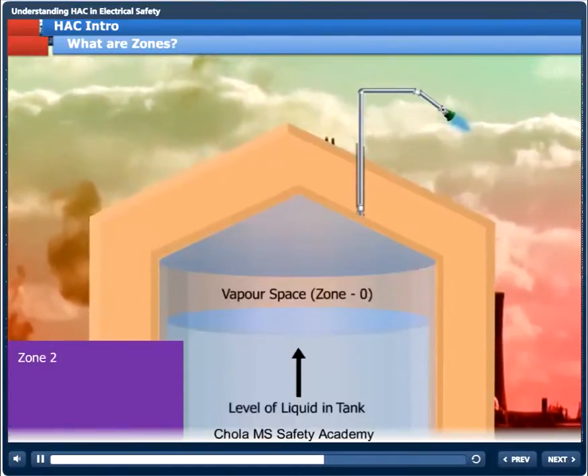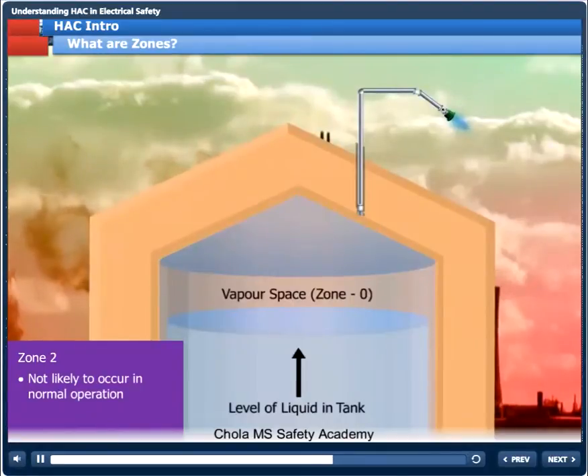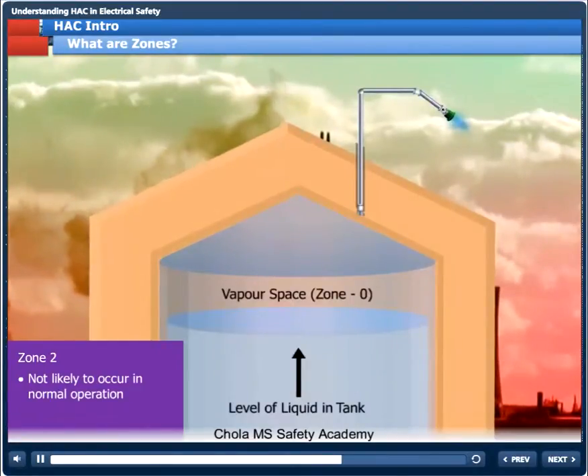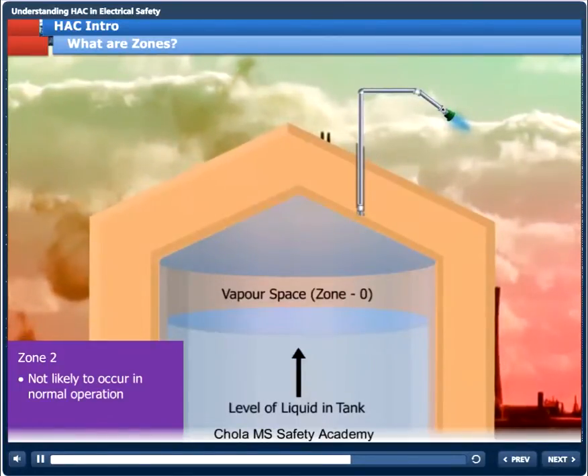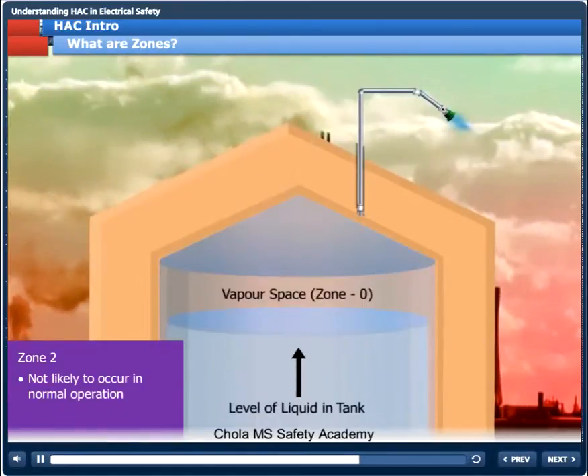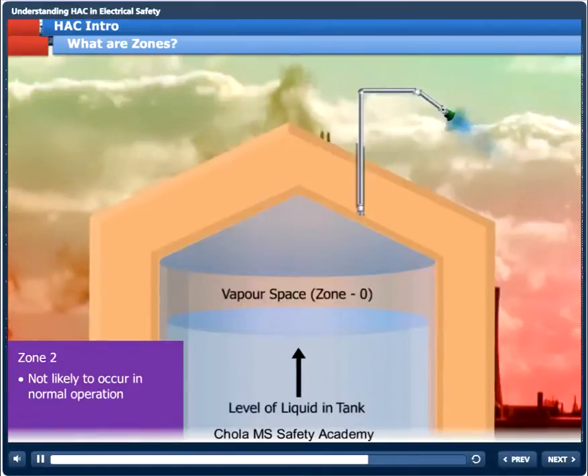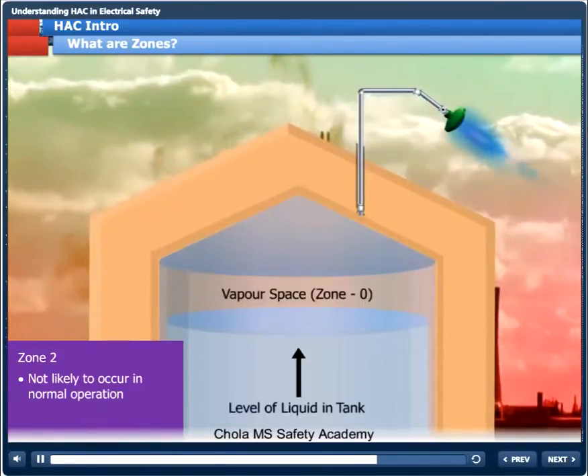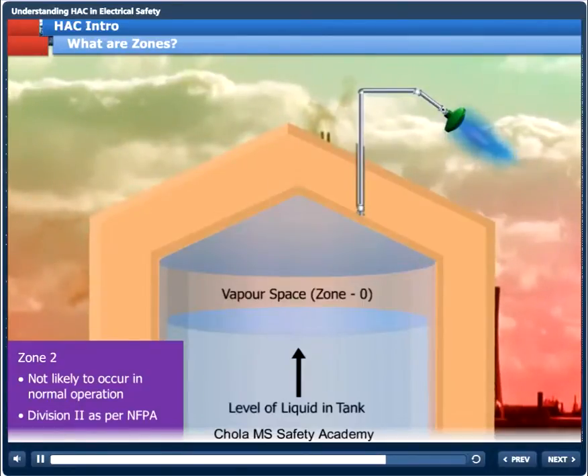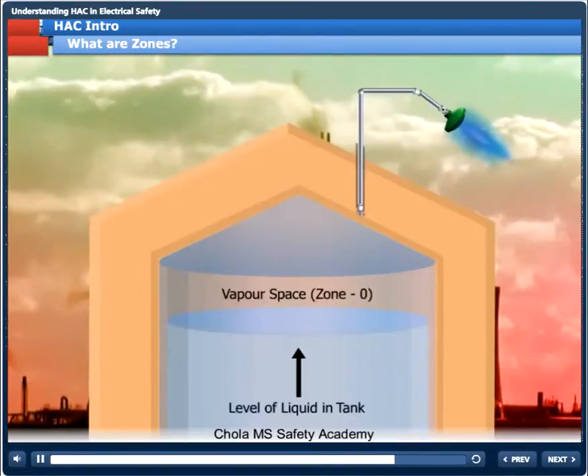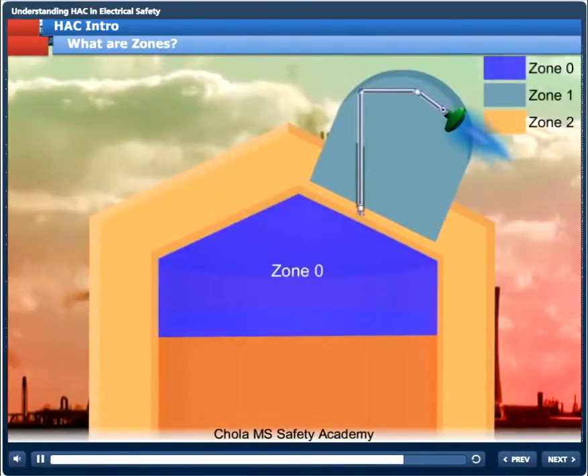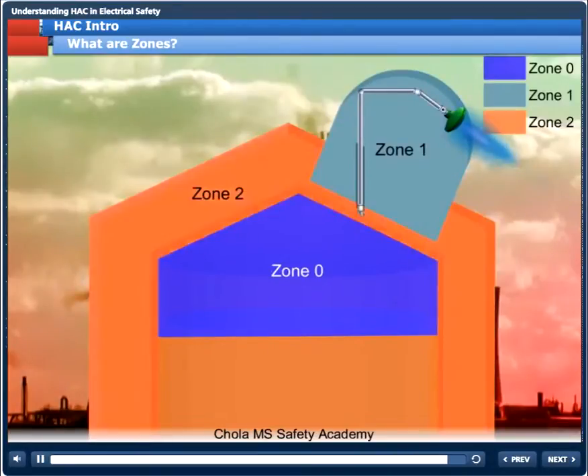Zone 2, area in which an explosive gas atmosphere is not likely to occur in normal operation, but if it does occur, will persist for a short period only. For example, the space around the vent of a tank holding flammable liquid may have a flammable vapor around it, exceeding the occasional limits only, for short periods of time. As per NFPA standards, Zone 2 is represented by Division 2 only. So, what we just learned is that, inside the tank is Zone 0, because there is flammable atmosphere always present. Around the vent is Zone 1, because the flammable vapor is present every time the level inside it changes. And very rarely, the flammable vapor is encountered in the Zone 2 area.